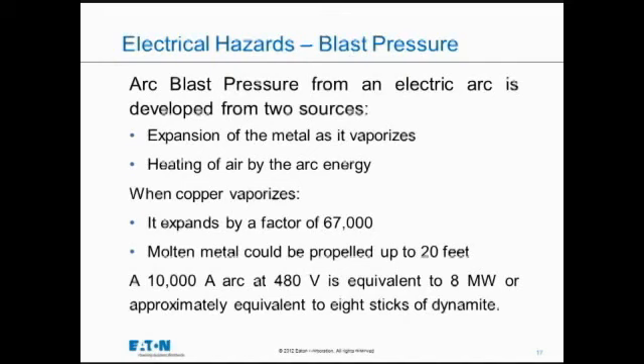Blast pressure coming from the arc flash is something that we know happens. There's explosions, and some of you have probably seen the Eaton products here that are called arc resistant, that contain the arc blast in the skin of the equipment, the front and the sides, and then exhaust it through a weak spot or a plenum to a place where it shouldn't harm anyone. Controlling this blast pressure can be done, but it's difficult, and we have some products at Eaton that can do that, called arc-resistant gear.